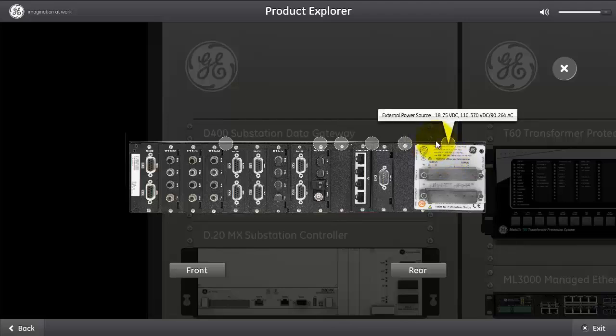As explained earlier, the D400 supports redundant power. The power can be external, provided to the D400, either 100 to 240 volt AC or 100 to 300 volt DC. We also provide the option for 20 to 55 volt DC. This is the top connections. The bottom connections provide a sensor for loss of power. So in case the D400 loses power, we can provide an output that would highlight that the D400 has lost the main power connection.